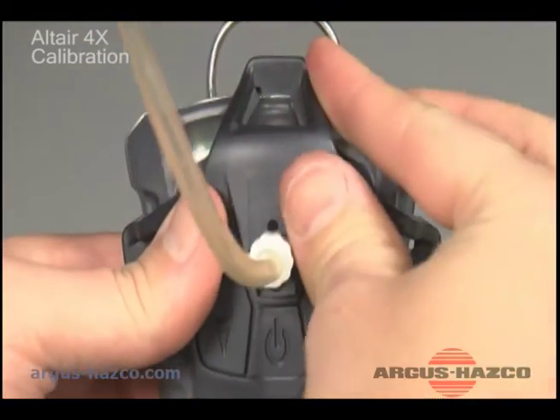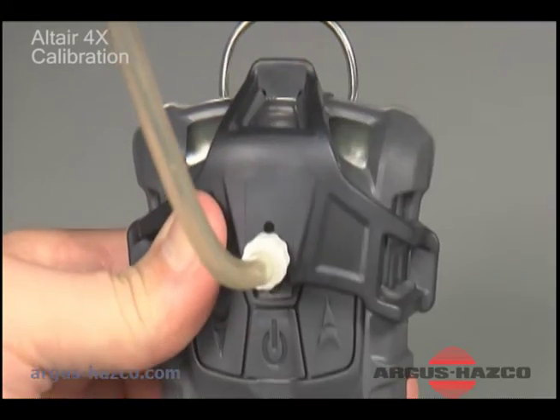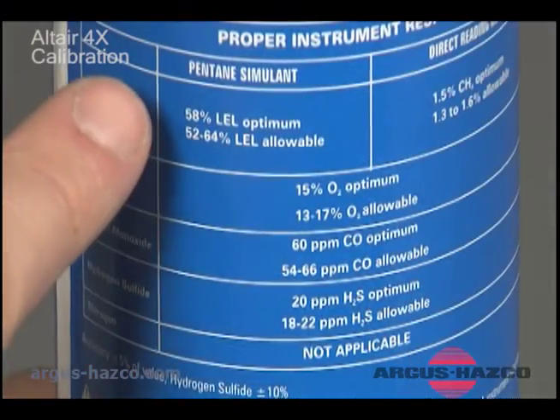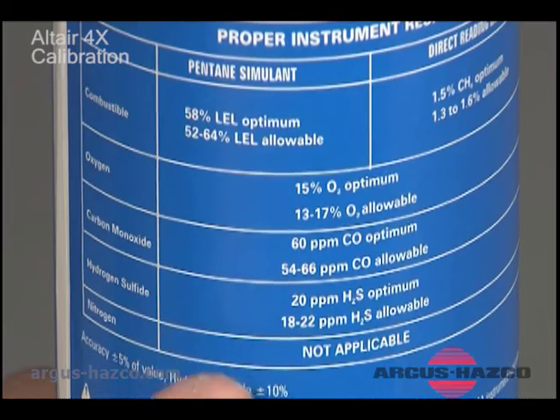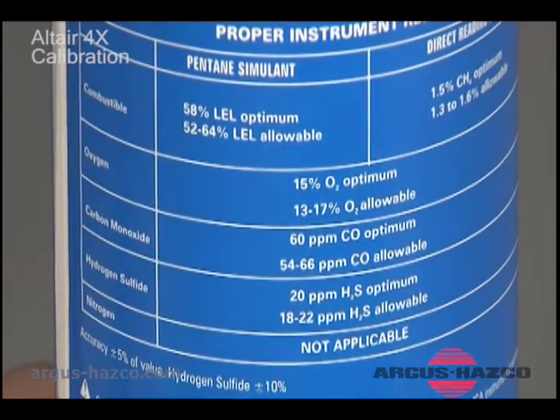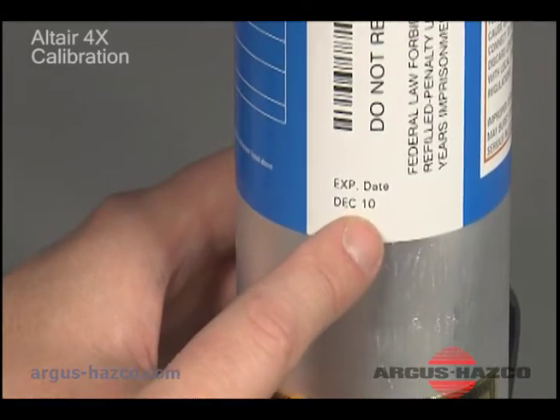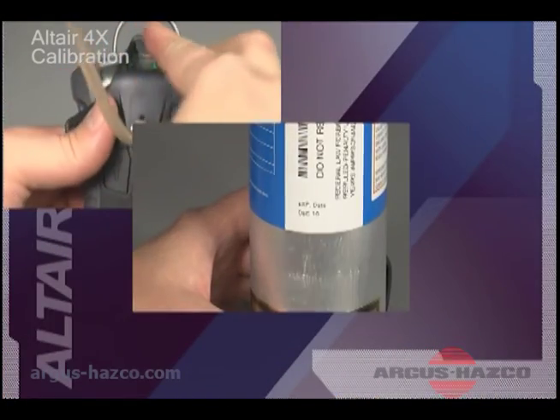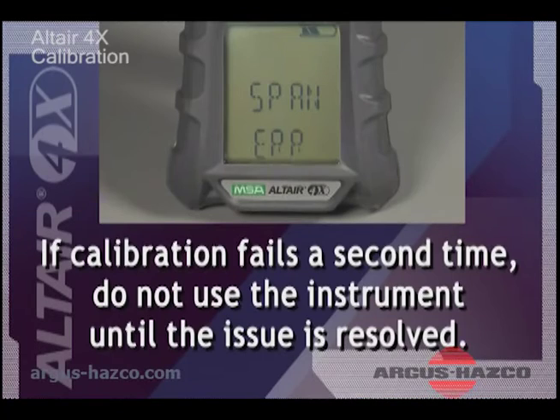If calibration failure occurs, be sure to check that your calibration cap is completely snapped into place on the instrument, that cylinder gas concentrations match those of the instrument's set calibration values, and verify calibration gas cylinder expiration date if applicable. After verifying all of these items, recalibrate. If calibration fails a second time, do not use the instrument until the issue is resolved.